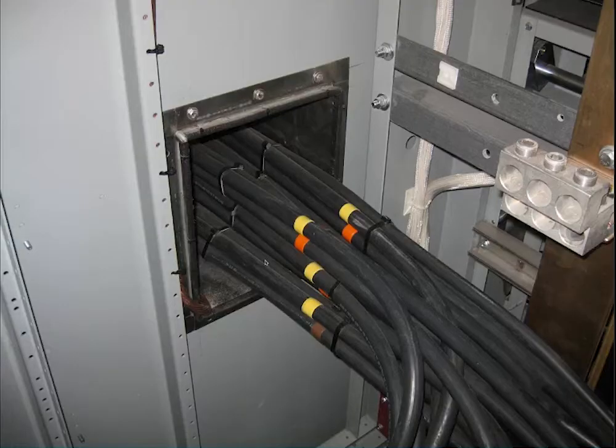So the picture that we show is what appears to be a 10 by 10 or a 12 by 12 wireway that is flanged into an upright switchboard section. And what you can see, it looks like six 500s per phase that are used in a parallel arrangement. And each one of those sets is grouped with its associated phase conductors. What this does is it minimizes the heating effects and the effects of imbalance, which could result in some conductors of the overall parallel arrangement being loaded more heavily than others because of imbalance.